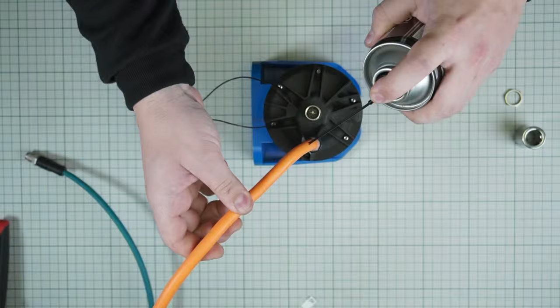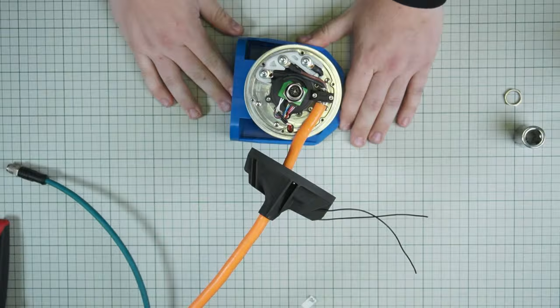The second thing you need to do is apply some silicone spray, just a simple silicone spray we use here, to lube up the wire a bit prior to attaching. Now you can undo all the bolts on the motor side. Once those are undone, you can slide the cap upwards. Just keep in mind the position sensor connector should be protected from any kind of damage. Once it's lifted up, you can move it aside, and you have the parts here.